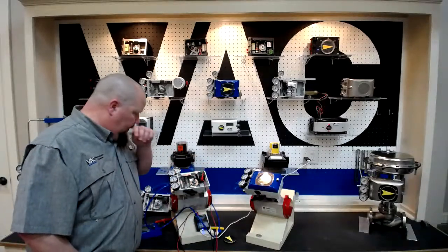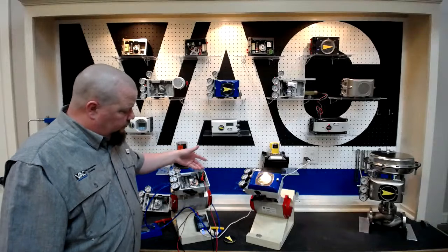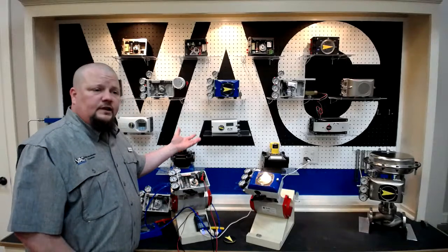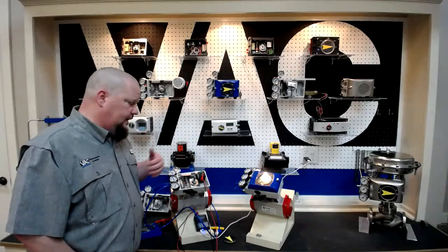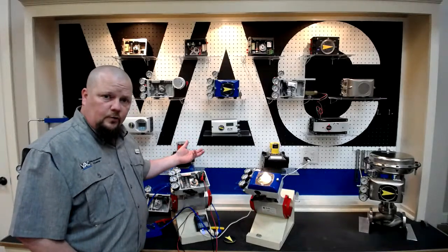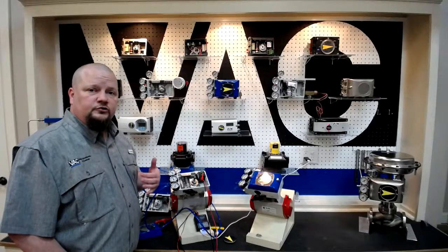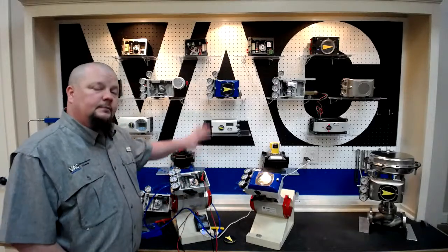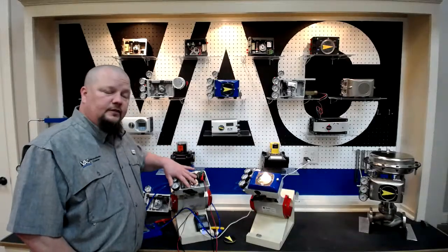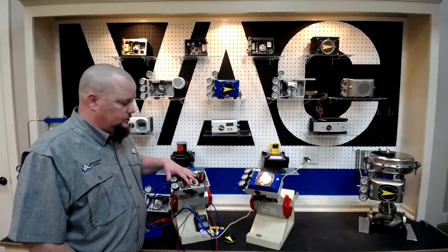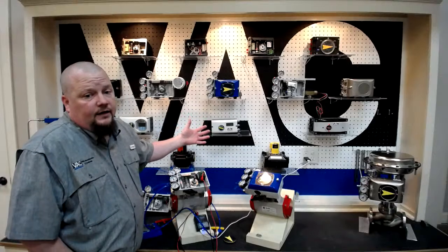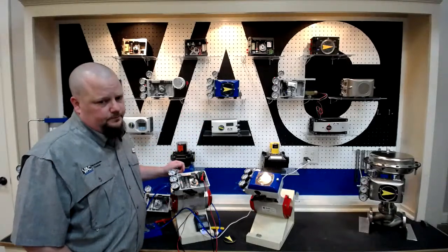And this is where I was speaking to earlier, where the control room is generally wired into the terminal strip, and you have to rely on that sometimes. But for me, I always want to remove the control room wiring and hook up my own signal generator. That way I know I'm getting a good, clean signal, and I can eliminate any issues. I can verify the functionality of the positioner without having to trust a variable that I have no control over.